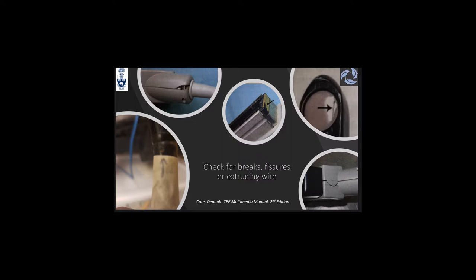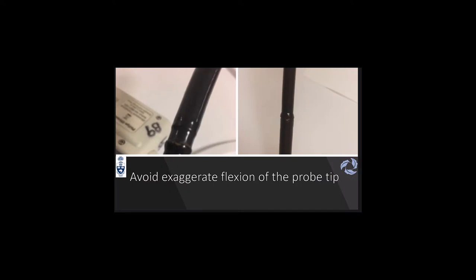As examples of equipment damage, you can see breaks, fissures, and cracks — all of these need to be checked before introducing the probe into the patient. If you exaggerate flexion of the probe tip, this is the most common result: over time the cover gets damaged and erosion occurs, which can cause an electrical issue.